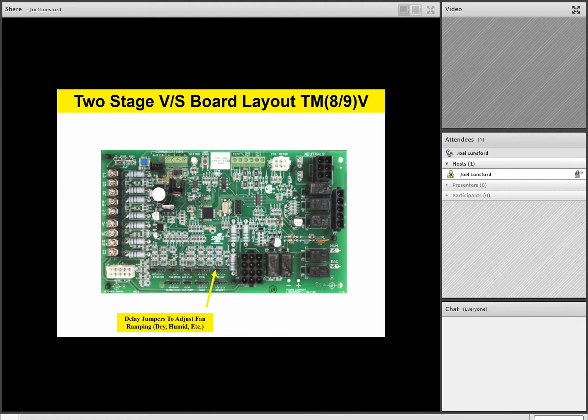If it's on the B function, which is a humid function, it's going to ramp that fan. It'll run about 1.5 minutes on 50% airflow. Then it'll ramp up to about 85% airflow for another 6 minutes, and then go on up to 100% airflow. And that ramping operation in that humid environment will give us a much colder evaporator. And what that does, it actually wrings extra moisture out. So that's one of the real big features of a variable speed product, is this variable speed blower motor. It allows you to customize the ramping or the on delay for cooling. And what it does, it allows you to really control extra humidity and so on in the space. So that's a really, really nice feature for variable speed. And so you'll set that up for cooling on delay with the delay jumper.